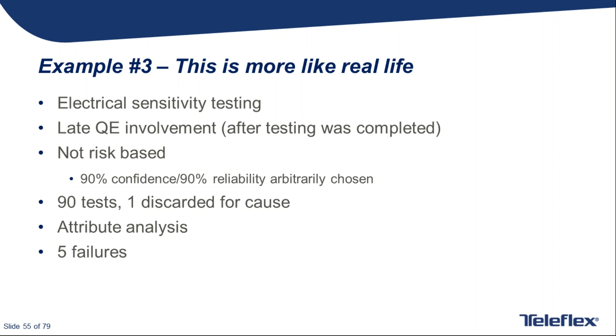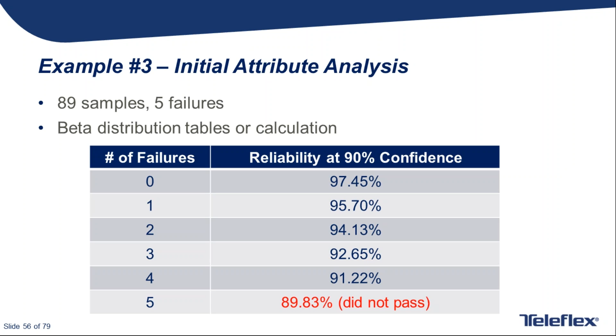So this is what the initial analysis looked like. Since there were more than 0 failures, the simple formula for a sample size as a function of confidence and reliability does not apply. However, reliability software or beta tables can be used to interpret the results. It was disappointing. There were 5 failures, and if there were only 4, the acceptance criteria would have been met, and maybe they wouldn't have even come to talk to me. But there were 5 failures, and you can't fudge the data. So another thing I wanted to look at and challenge was whether the acceptance criteria were correct and defendable in the first place, and whether variable testing can provide better decision-making information.